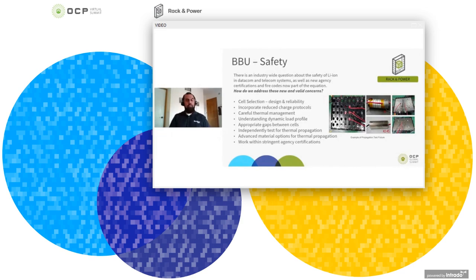Some of our BBU cells have been on test for more than 5 years at different temperatures to understand the performance over that span of time. Another thing we do to ensure more safety within the BBU is we reduce the charge voltage on non-lithium iron phosphate cells. Lowering the charge voltage extends the life of the cell and also increases the safety factor. And then to ensure proper thermal propagation design mitigation, we apply gaps between cells and use thermal barriers to prevent heat from one cell affecting the neighboring cell.